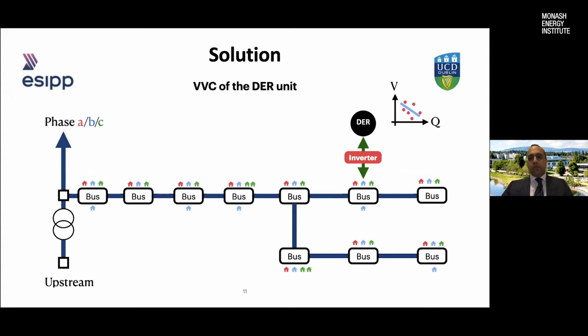So the solution we proposed for this project, as you can see in this slide, was to find an intelligent way to control the reactive power of DERs, or distributed energy resources, which are connected to the distribution grid. So we came up with a volt-var curve, as you can see here on this graph. We found the relation between the voltage at the connection point and the reactive power that the DER should inject into the grid or absorb from the grid. So these DERs measure the voltage at the connection point, and then they understand how much reactive power they should inject into the grid or not, based on the objective function that we specify for them.